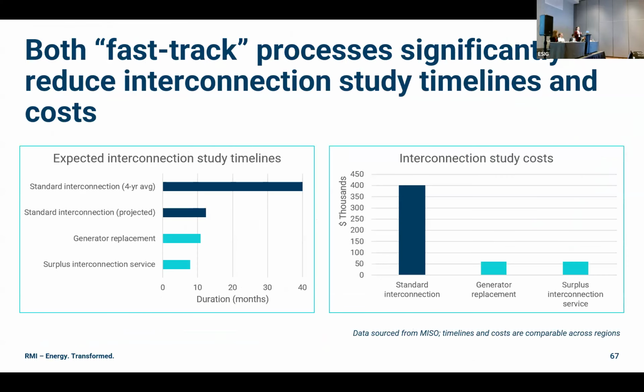So what is the improvement of these two fast track type processes? Well, they reduce interconnection study timelines and costs. On the left, you can see the x-axis is months. We have an average of about 4 years typically for interconnection these days, even though it's supposed to be around a year and a half. With generator replacement and surplus interconnection service, those processes are much shorter and curtailed compared to the normal standard interconnection process, so you can get through a lot faster. And with costs, standard interconnection costs are in the hundreds of thousands, whereas for generator replacement and surplus service, it's much less.